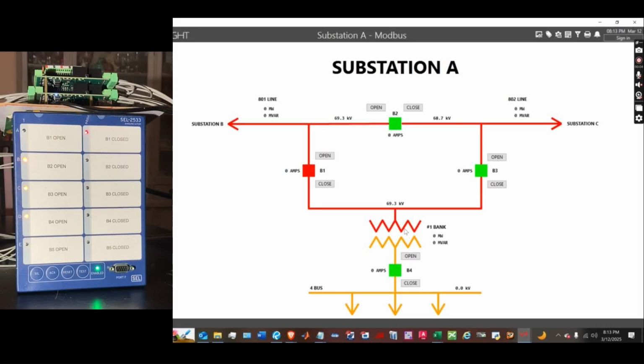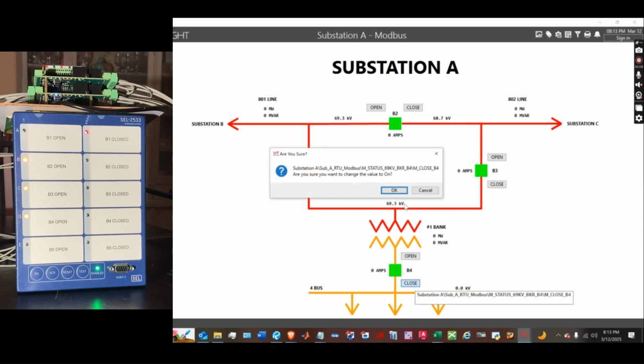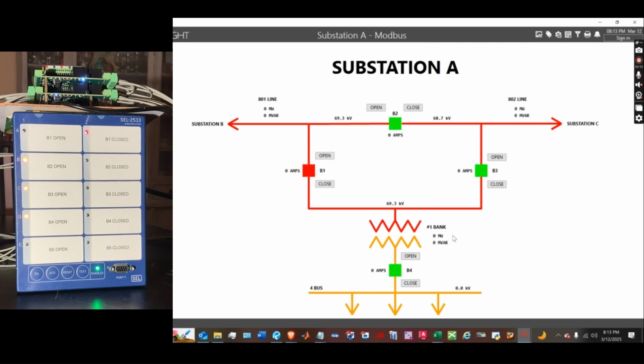Since there's still no path for load flow, all the breaker currents and the megawatt and megavar values remain at 0. Now breaker B4 is closed, allowing the 13.2 kV distribution load to be picked up from the 801 line. The megawatt and megavar values on the 801 line and number 1 bank transformer now show that 10 megawatts and 2 megavars are flowing into the distribution system. The currents through breakers B1 and B4 are also displayed. These currents are based on the system voltages, load flow, and the available paths.